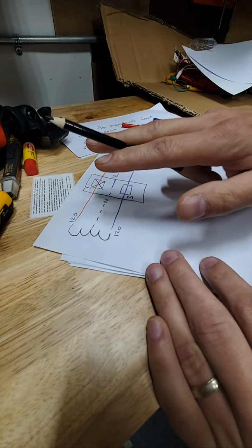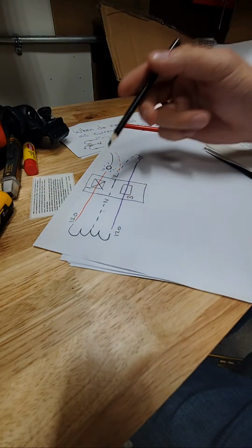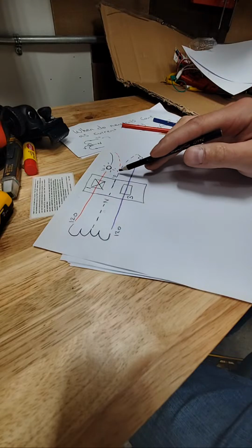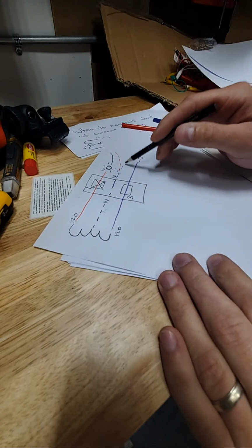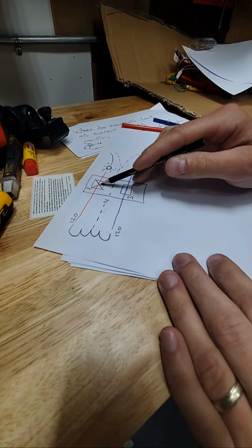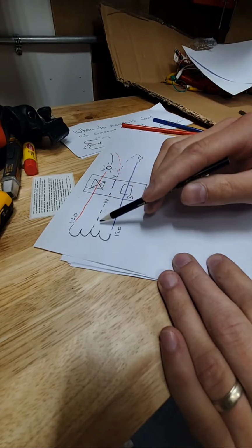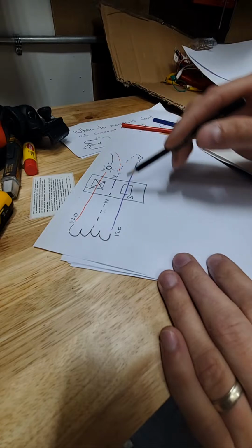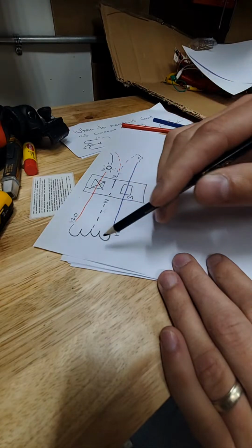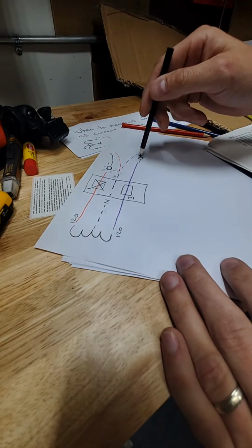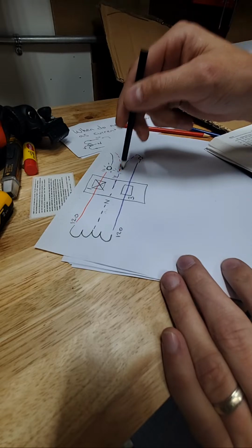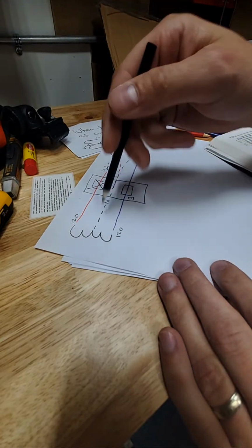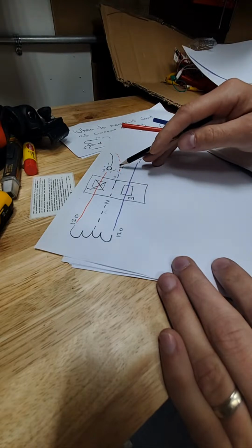So we got two necessities here. One, we need to simultaneously disconnect. That way you can work safely in this box, because you don't want to consider this current carrying because you're sharing the neutral, and you don't have to per the code. But if you turn off one of these breakers by itself, now this becomes current carrying because you're no longer carrying the imbalance. You've turned this into a 120 volt, neutral circuit where you're back to the same boat as what we started with.